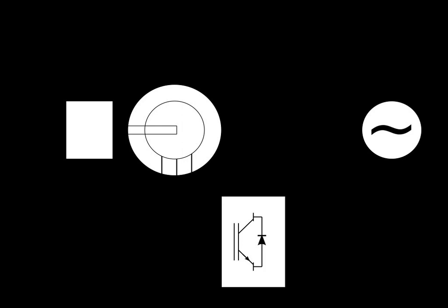By using the converter to control the rotor currents, it is possible to adjust the active and reactive power fed to the grid from the stator independently of the generator's turning speed. The control principle used is either the two-axis current vector control or direct torque control, DTC. DTC has turned out to have better stability than current vector control, especially when high reactive currents are required from the generator.